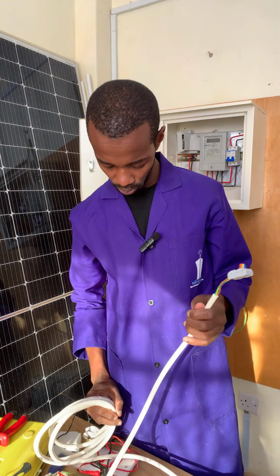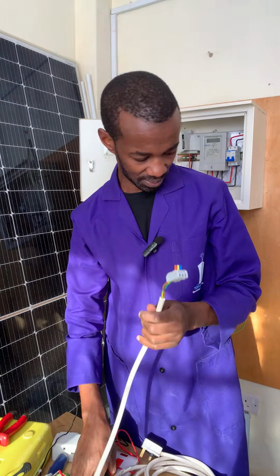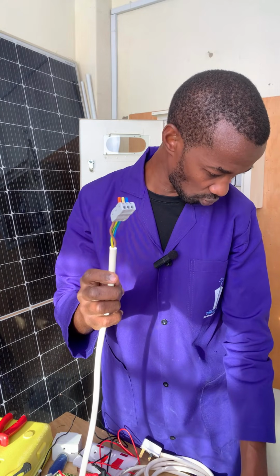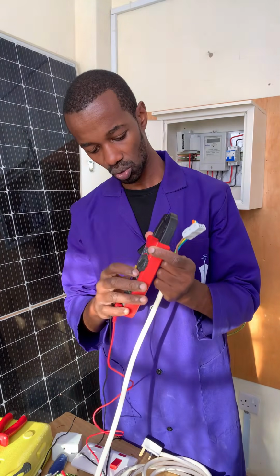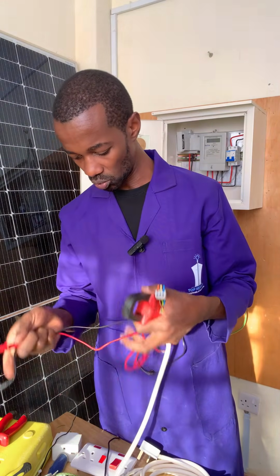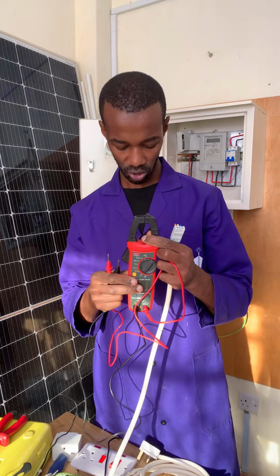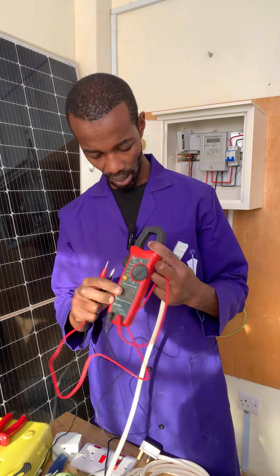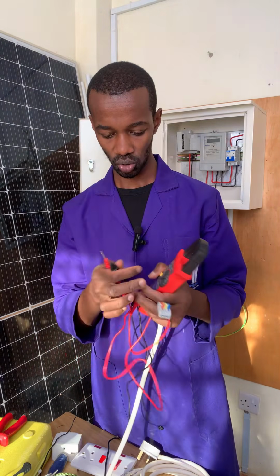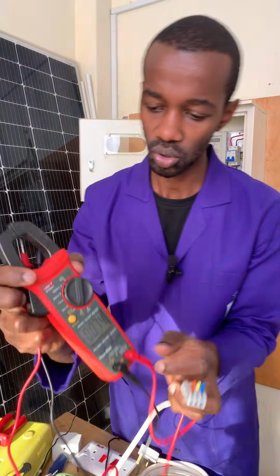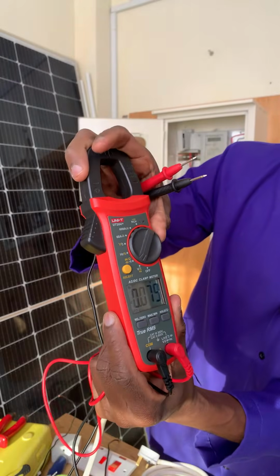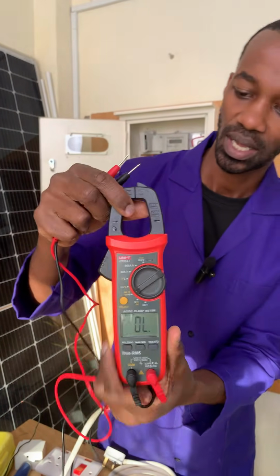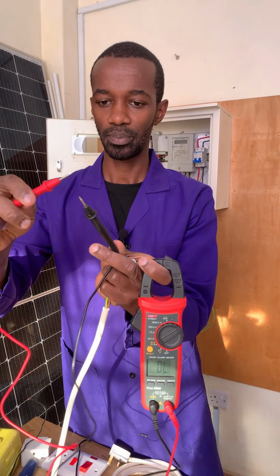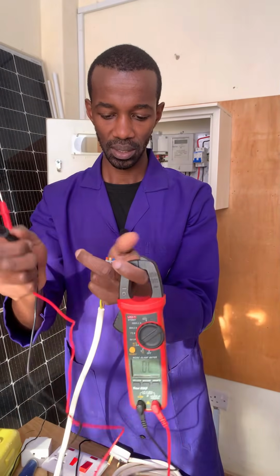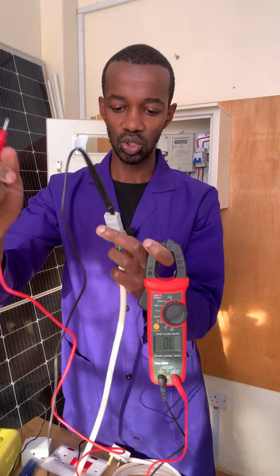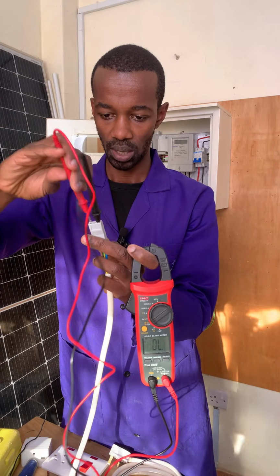Now we want to prove that they are not short-circuiting themselves inside the WAGO connector, so we simply test end to end. This is partly a lesson where you will learn a lot about using a digital multimeter. Here I'm also using a multimeter or clamp meter to test for continuity. You simply turn this knob for the continuity test. How do you know it is continuity test? The moment you bring the probes together in contact, there's that beeping sound. So if we test between the terminals, it should give us open, no beeping sound, meaning there is no connection between the wires.